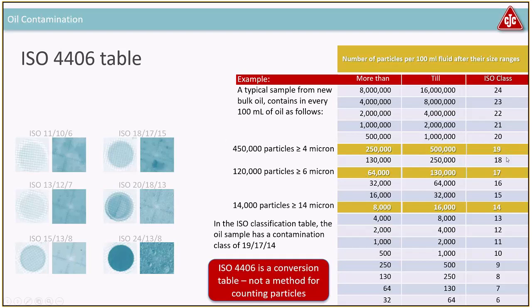Cleaning an oil from, say, 19/17/14 to a class 16 — you reduce by half, half, and half again. That's 64,000 compared to half a million particles — quite a fall. I like to have both the number of particles and the class.